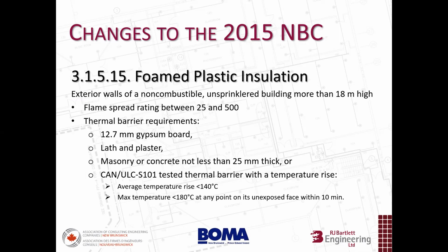For exterior walls of non-combustible unsprinklered buildings more than 18 meters high, as long as the foam plastic has a flame spread rating between 25 and 500, these are the thermal barrier requirements that apply, similar to what we just saw, but now with a bit of an increase where a minimum thickness of the masonry or concrete is specified. We also have some criteria from the CAN/ULC S101 thermal barrier test, where they limit the average temperature rise on the unexposed side of the thermal barrier to an average of 140 degrees Celsius or a maximum temperature rise of 180 degrees.